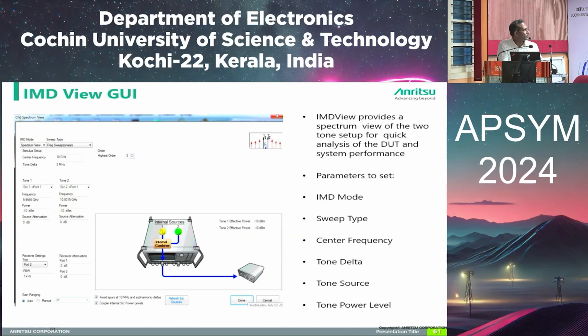So this is the setup we have internally. We can set the CW frequency, and we can set the two tones with different frequency offset values and different power levels, and feed them to the DUT. These are two internal sources and a combiner, and it will be fed to the DUT. Then we have to set the receiver value. It will be connected to the other port of the VNA itself directly, and we can measure the receiver also. So it will act as a spectrum analyzer inside the instrument.